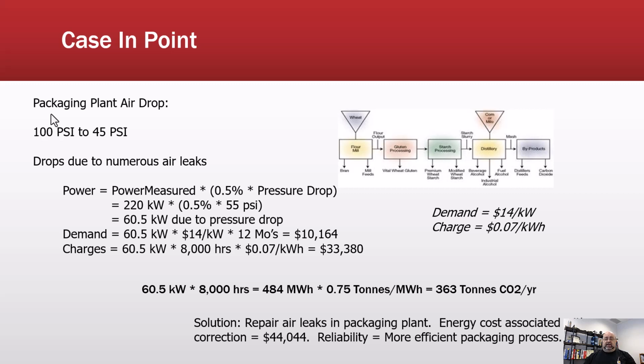So in this case, unless you're looking at steam turbines, that we'll cover in another presentation, let's just say it's all electrical. So let's say 0.5% times the pressure dropped times the power measured gives me the actual losses associated with that pressure drop. If I take a look at this particular application and I have 220 kilowatts, and by the way, part of the problem we were running into and investigating is that the air compressors were heavily overloaded. That 60.5 kilowatt drop means that is 60.5 kilowatts we don't need to be using.